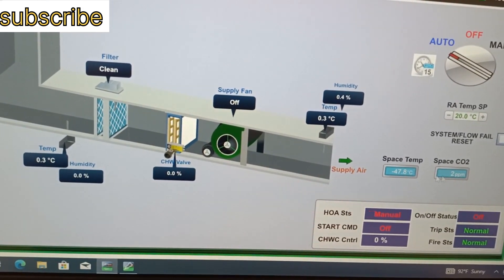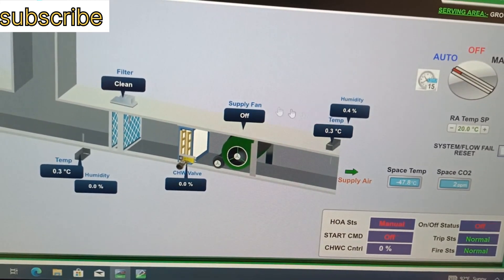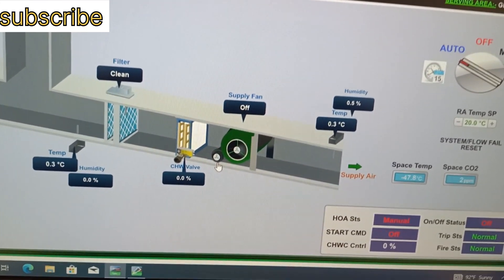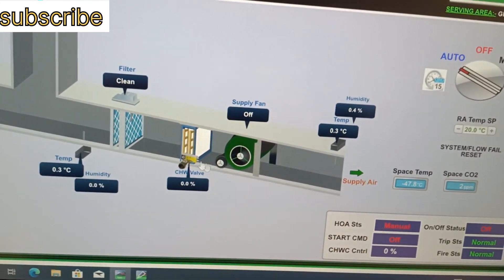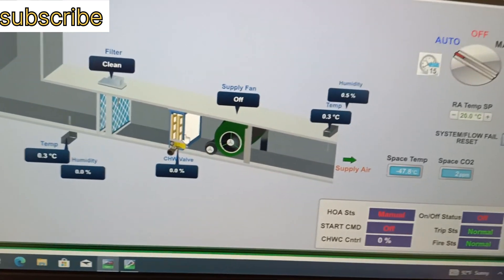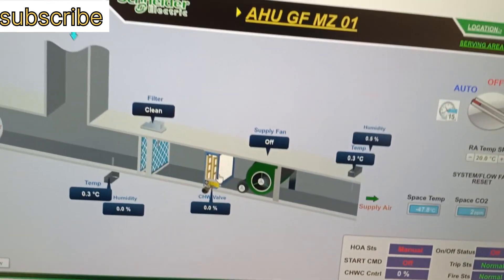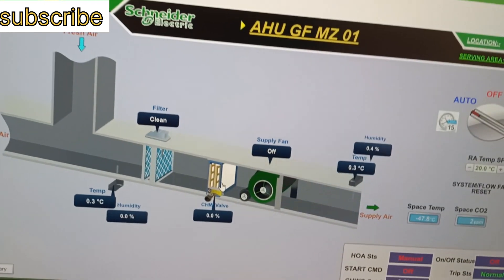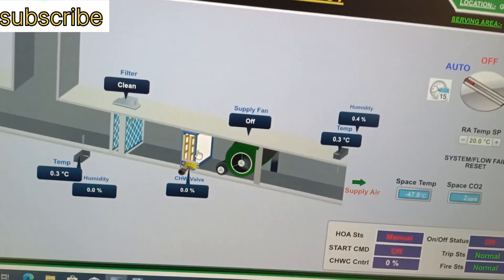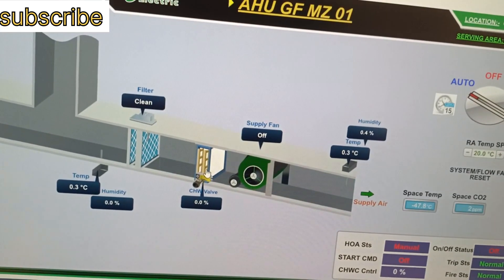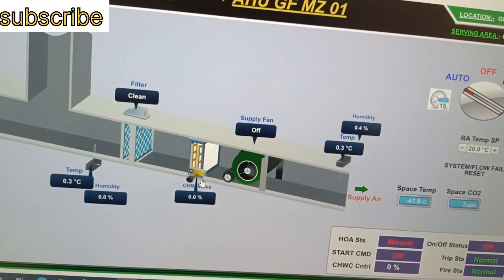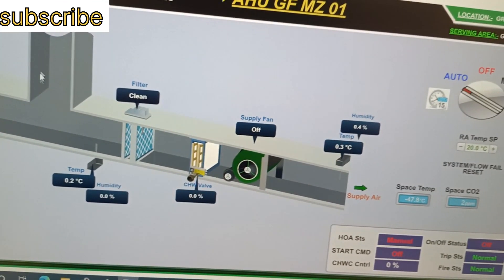This unit has been disconnected from the old machine and a new machine has been connected to the new BMS system. Since this was the old unit, it is not showing correctly here, so we need to delete it from the program.